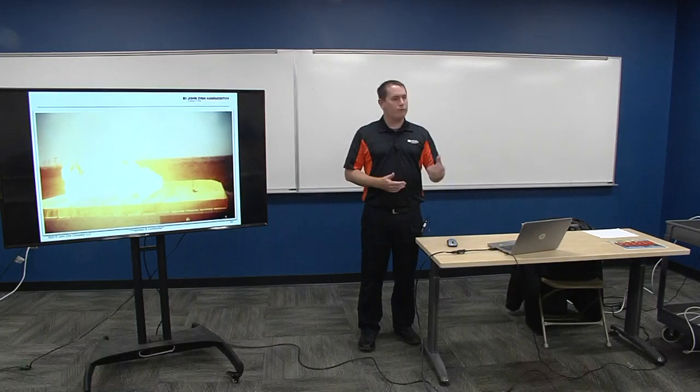So I've got an example for you. It's kind of cool. We had an operator actually out in the field on a site. You don't get to see it very often. And this was several years ago, probably back in the 90s or whatnot. But he was working on a process heater, and there happened to be a ground flare. He knew there was an upset in the plant because he was on the heater. He knew it was coming. So he just turned around and took some photos of this staging event. Normally this flare is flaring on what we call the first stage flare over here. But as there's an upset coming, that shuts off, and it goes to all these little pressure-assisted burners. So this is as the flow starts to come, but as the flow increases through the line, right, we bring on more burners and more burners and more burners until everything's one nice big fire, right? That's the full capacity of the flare, but it allows it to burn efficiently because you're only commanding the amount of burners needed for that efficient combustion.